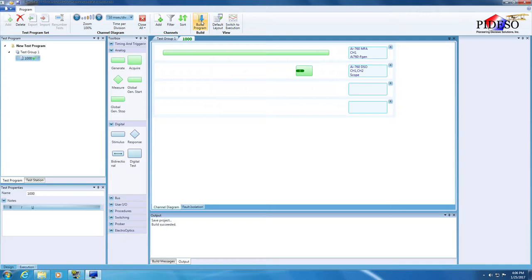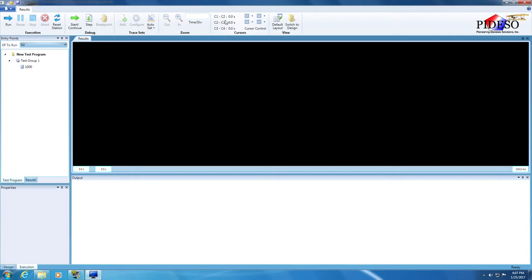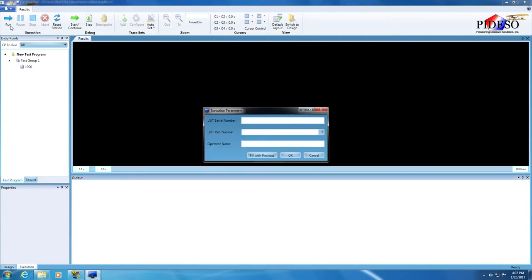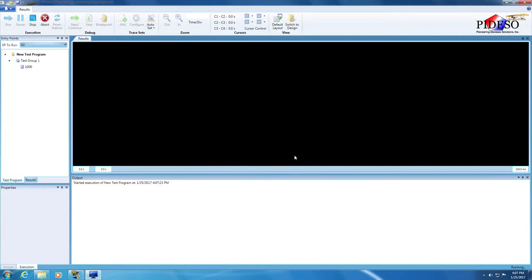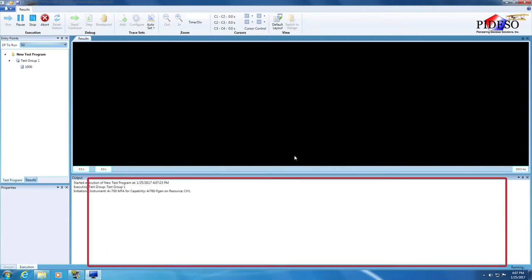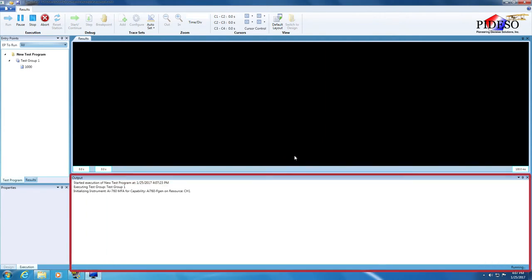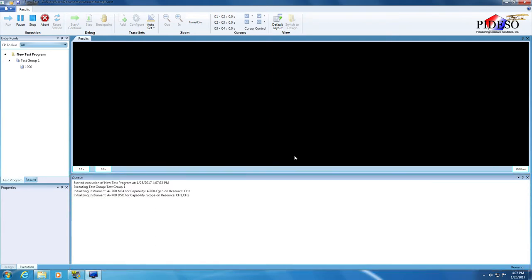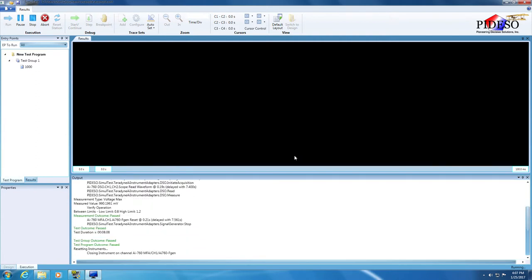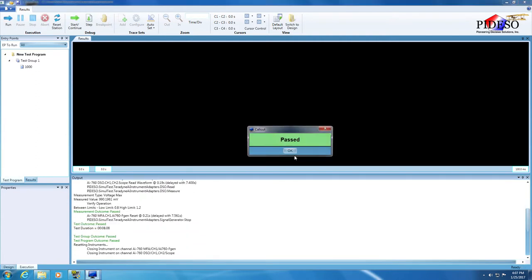The next step is to run the TPS. Activate the execution view by clicking on the switch to execution button in the application toolbar. Press the run button in the application toolbar to start TPS execution. The execution parameters dialog will be displayed. Here is where the operator enters execution data that has relevance only for reporting purposes. Leave the fields empty for now and press OK. The execution progress will be indicated in the output area via execution messages. If the execution passes, this will be indicated with a dialog box stating that the TPS has passed. All the tree nodes in the execution tree will be displayed with green bullets, and the execution messages displayed in the output area that indicate the measurement, test, test group, and TPS outcomes will be displayed in green.